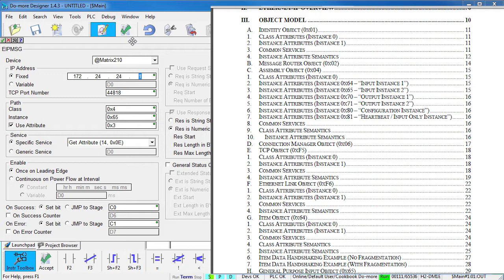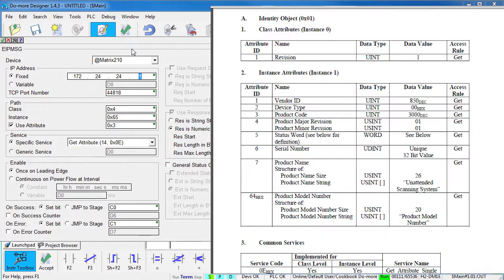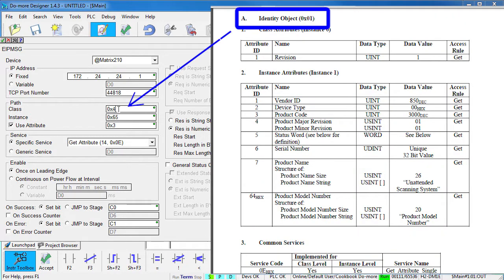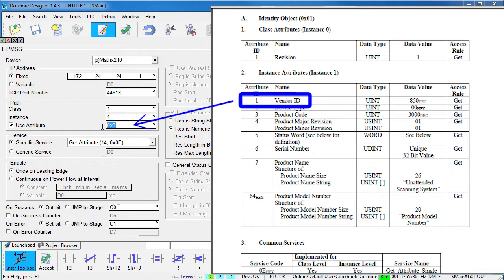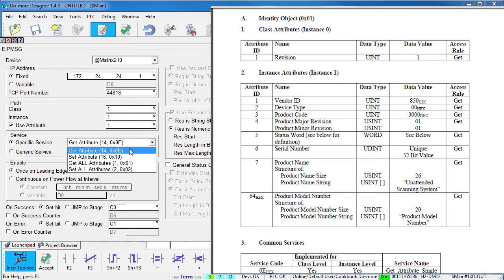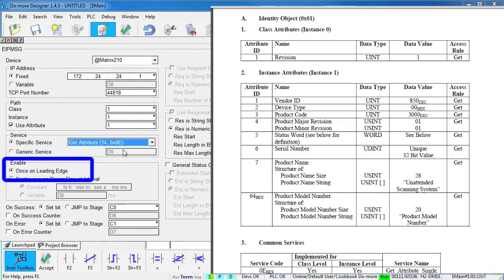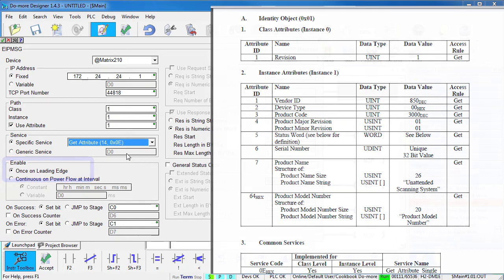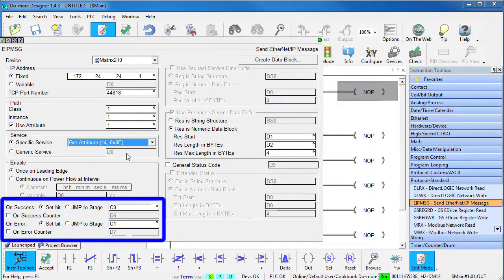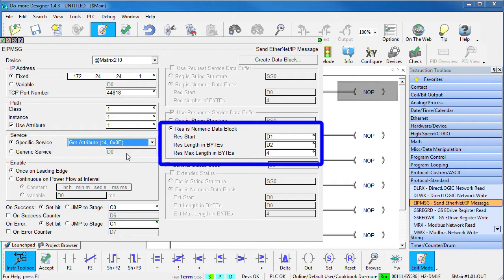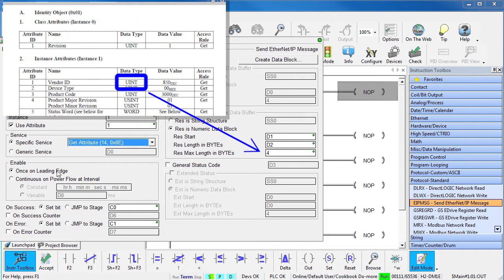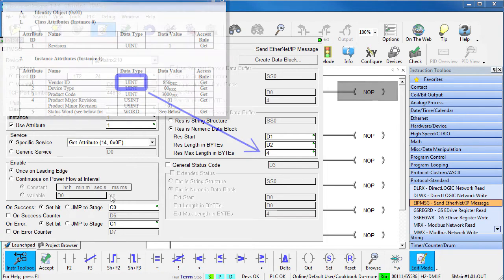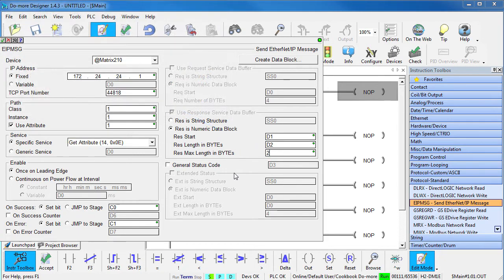Let's do something simple for our first example. Let's get the Vendor ID which is always in the identity object. And here it is. Looks like we need Class 1, Instance 1 and Attribute 1 to get the Vendor ID. We want to get this information and we'll do it on the leading edge of the ladder contact. We use these status bits and we'll put the Vendor ID in D1 and the number of bytes actually returned in D2. The Vendor ID is an integer so we expect a maximum of 2 bytes.